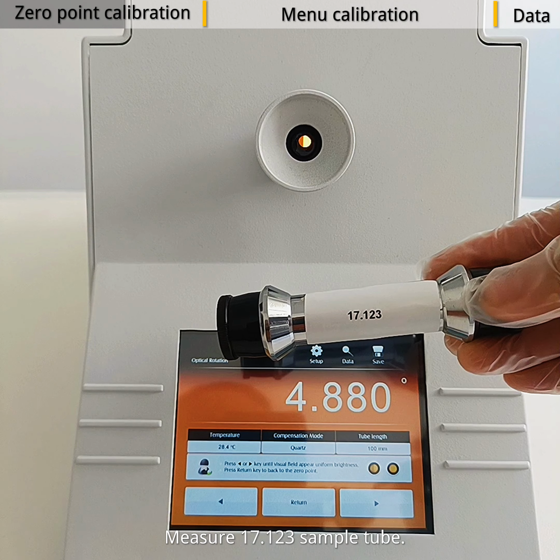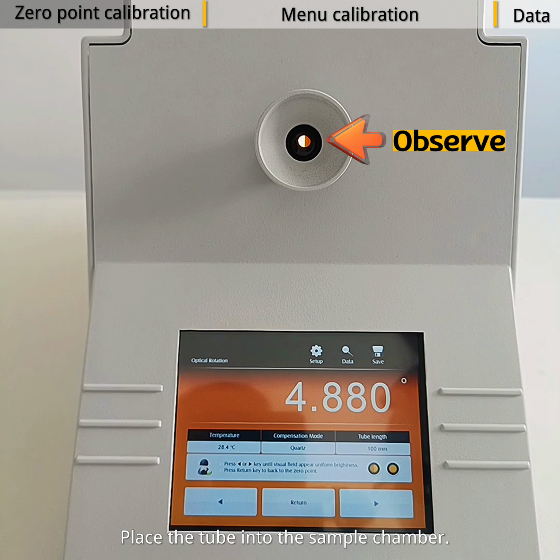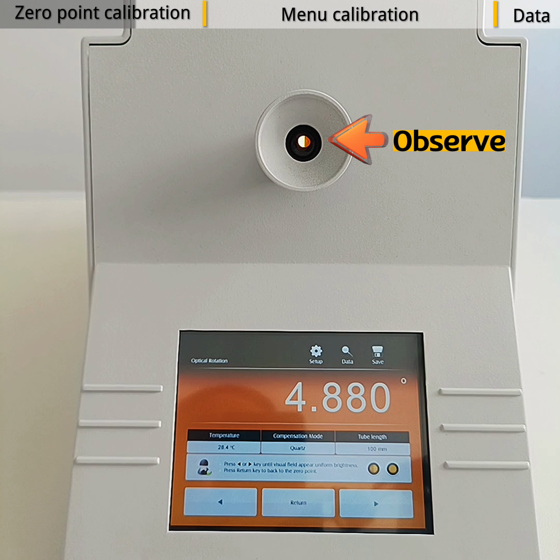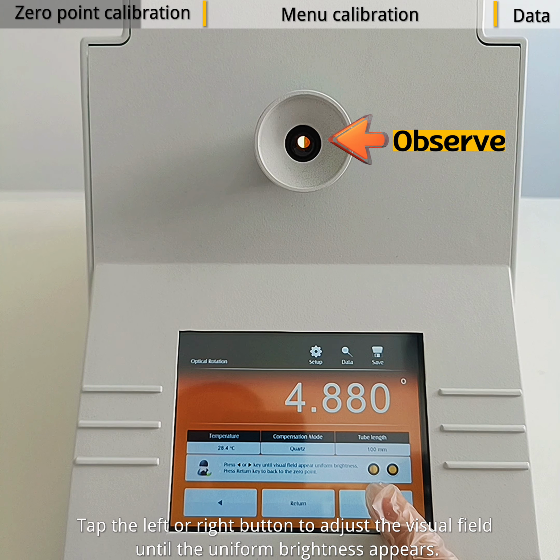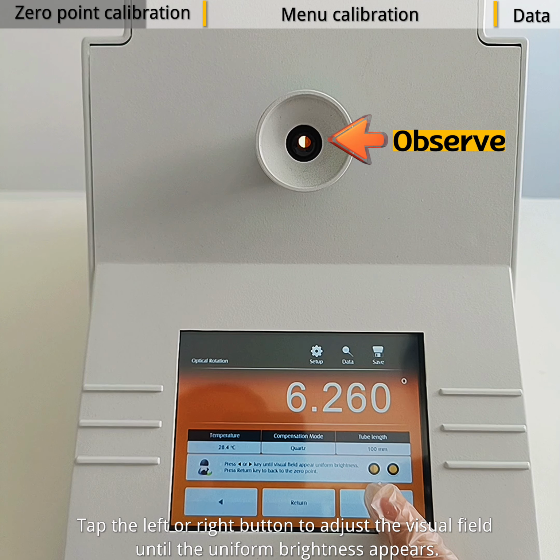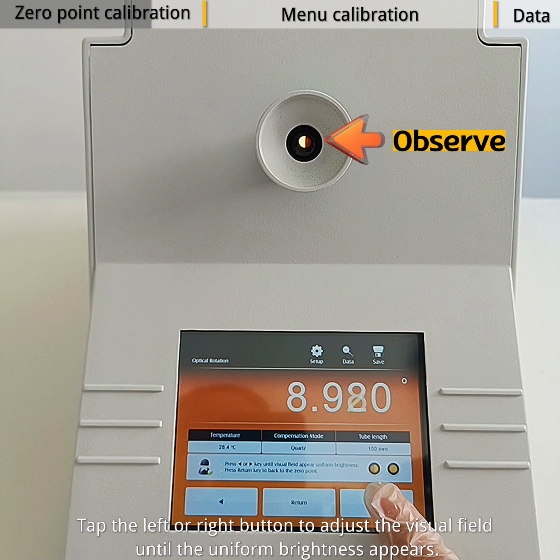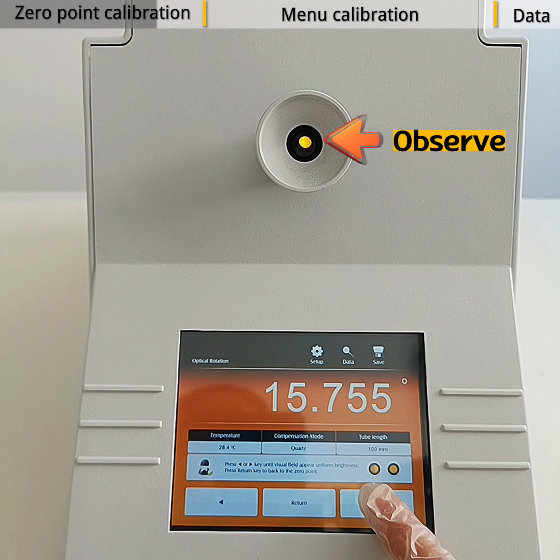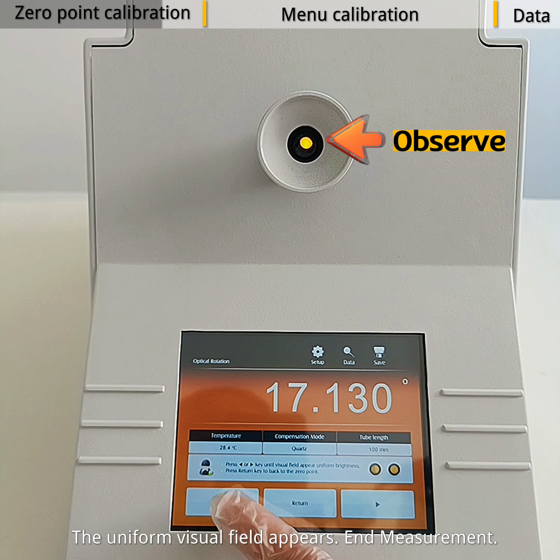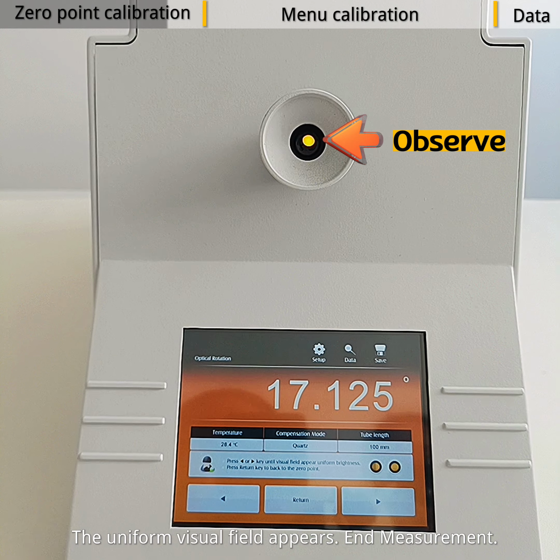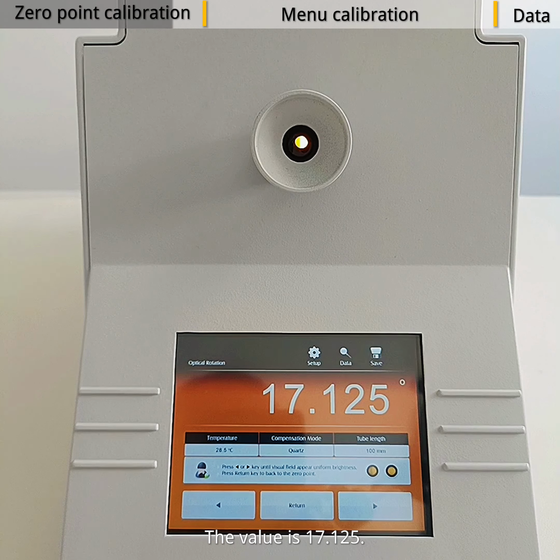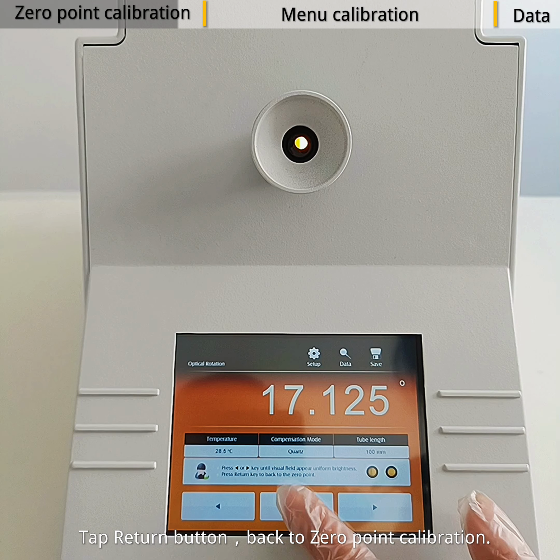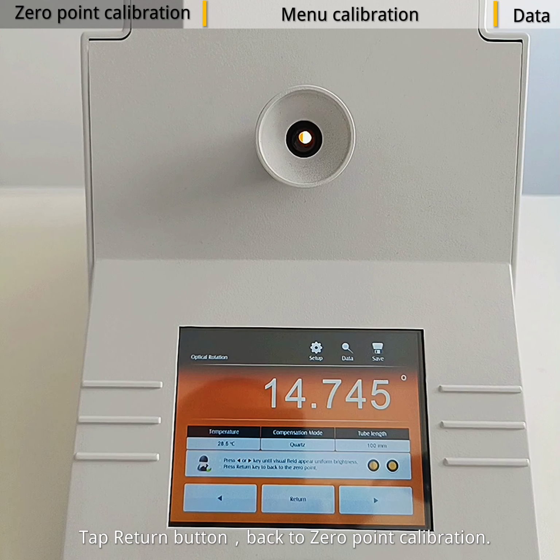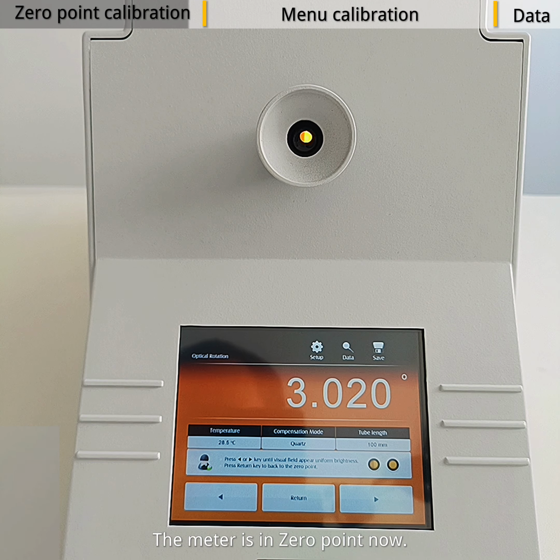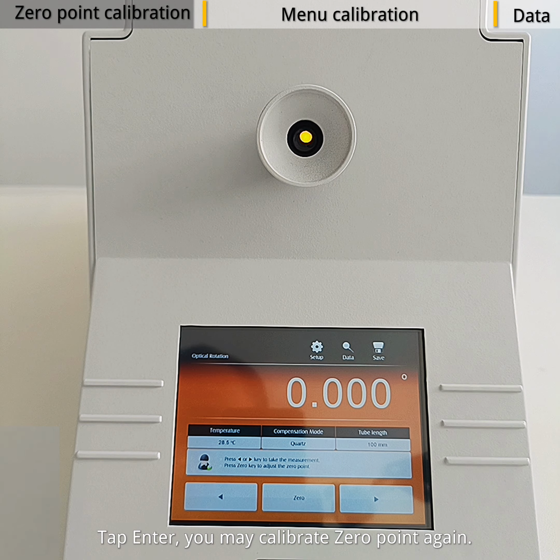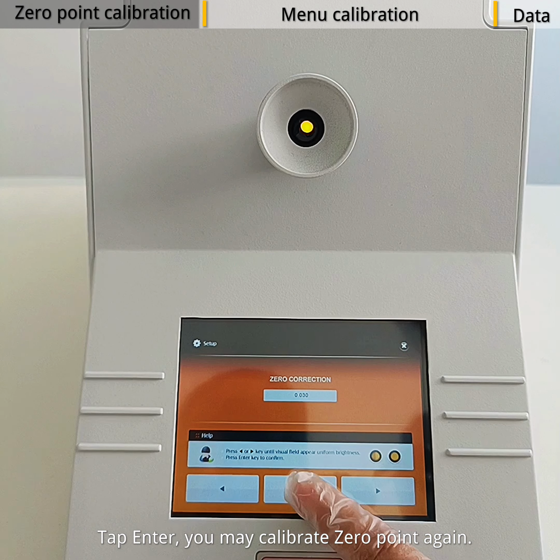Measure 17.123 sample tube. Place the tube into the sample chamber. Tap the left or right button to adjust the visual field until the uniform brightness appears. The uniform visual field appears. End measurement. The value is 17.125. Tap Return button, back to 0-point calibration. The meter is in 0-point now. Tap Enter, you may calibrate 0-point again.